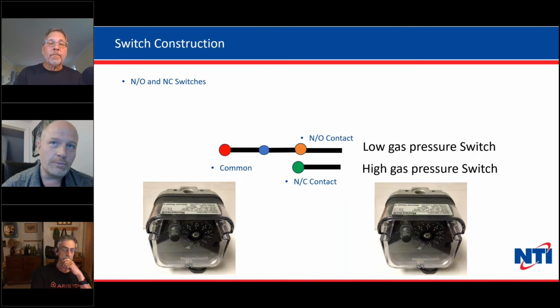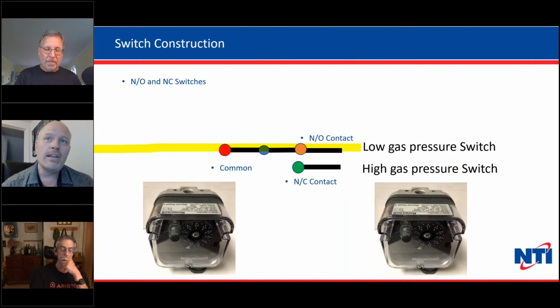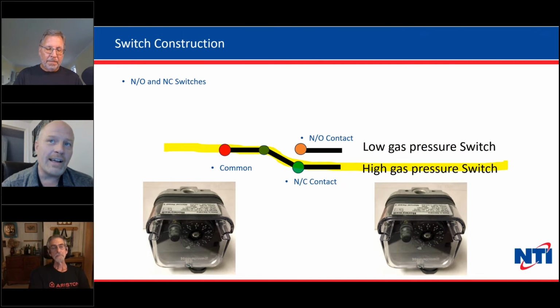So again, these switches are normally open or normally closed. We only use 2 wires on them, and we wire them as both normally open and normally closed, depending on where it mounts within the boiler. So there's our low gas pressure switch, which is typically normally open, and the high pressure switch is typically normally closed. I actually asked engineering, is there a particular preference for when you'd use normally open versus normally closed? And really the answer is it just depends what the controller that the boiler is working with likes.